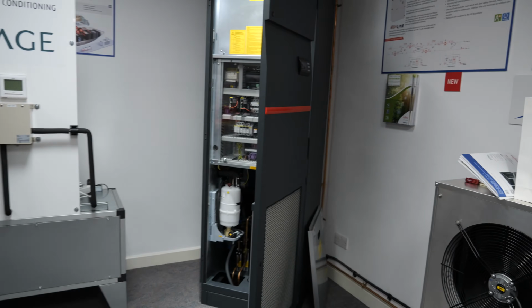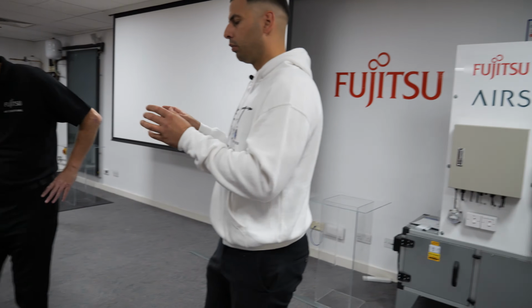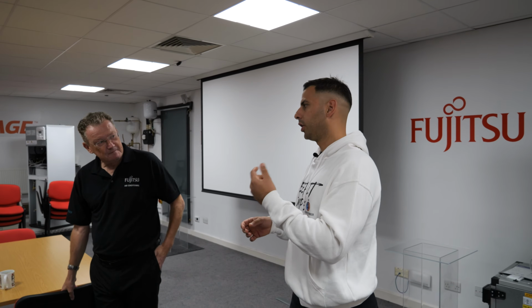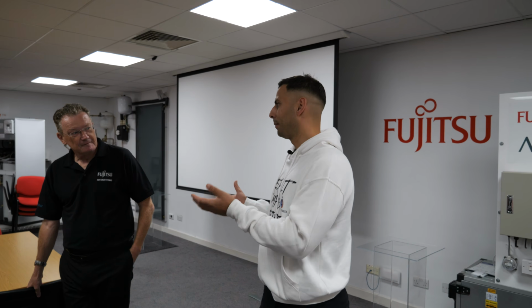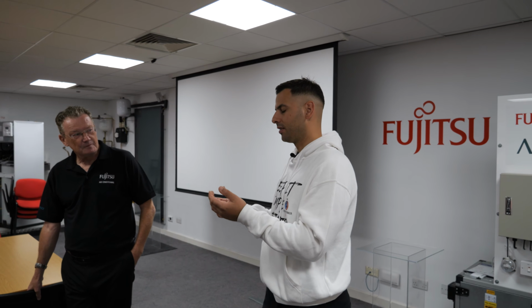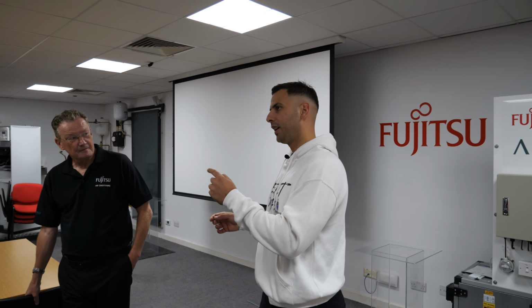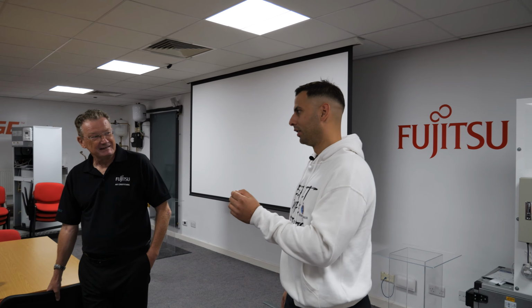Predominantly a trend system would usually, on AHUs we always monitor the return air temp. So the return air temp is what we're using as the ambient sensor. If we're trying to get that room to 21 degrees, we can either do it from the return air temp, but we can also fix the air temperature coming out of the unit to 21 degrees - supply temperature control.